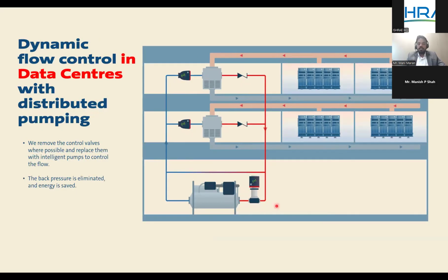Let's see quickly how we can bring about a change. Same schematic, the primary remains the same. The pump is driving the flow to the chiller, but the only change is that the primary pump is limited to the distribution of chilled water in the plant room. The line which you see, which is dividing the primary, the production loop, and the secondary, is a decoupler or a bypass. So the primary pump is designed only to cater to that. And if you see, we have removed the balancing valve and flow control valve, and we have connected dedicated distributed pumps or coil pumps to each load.